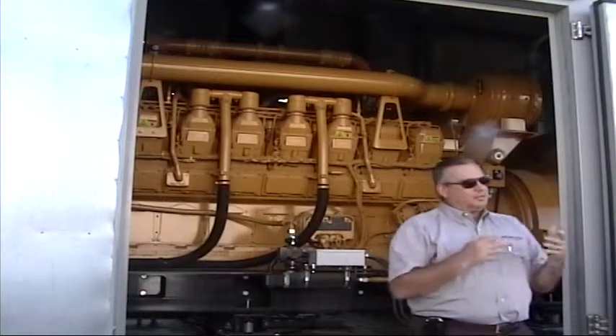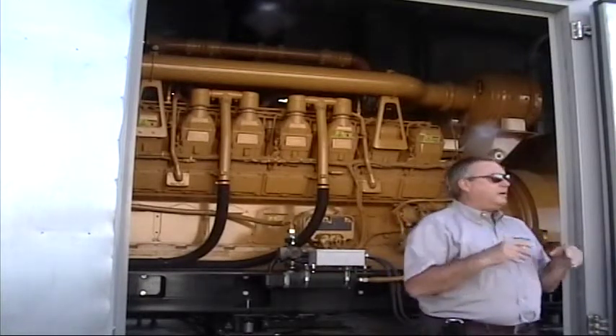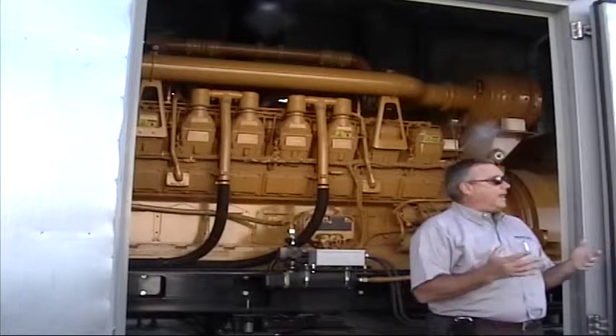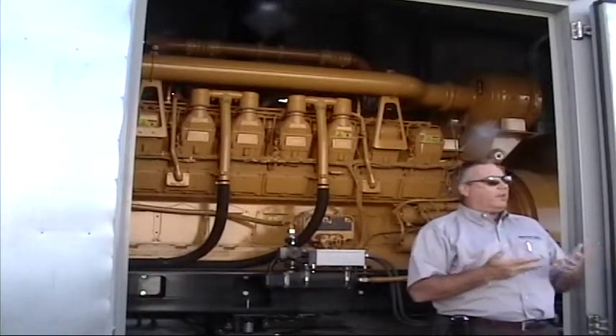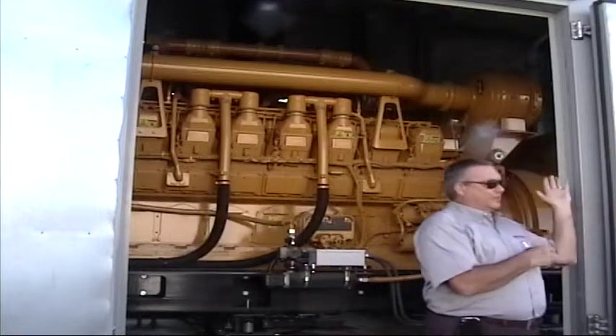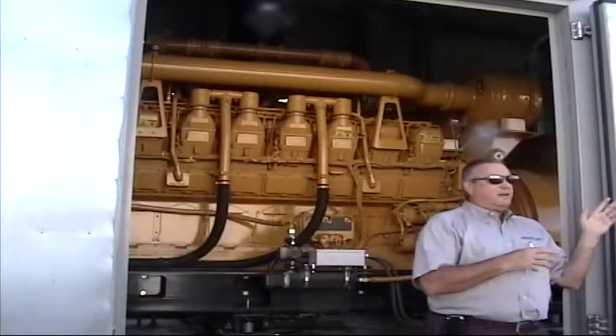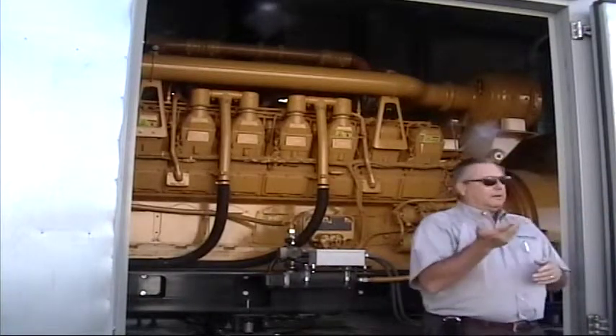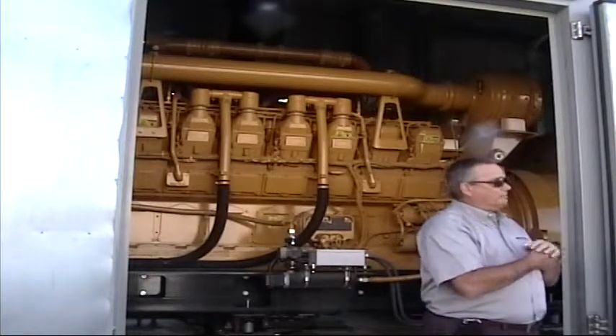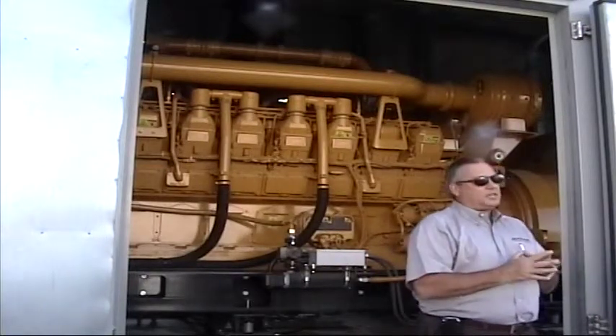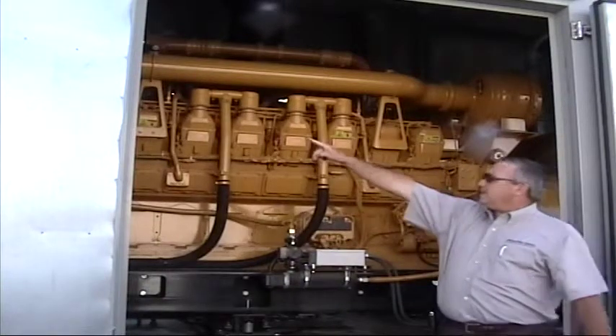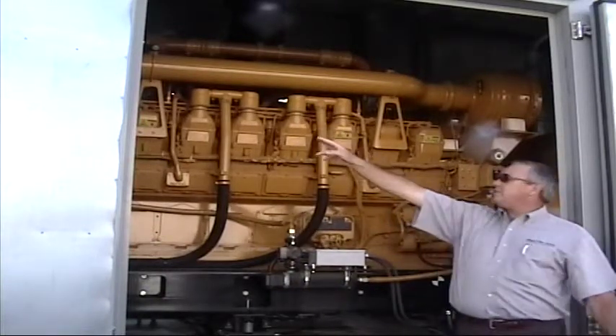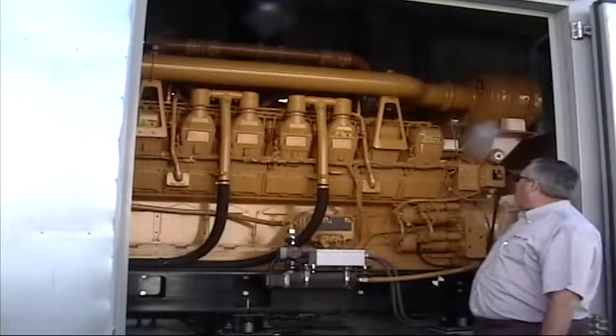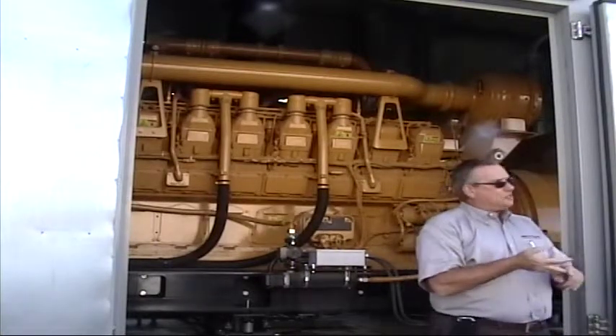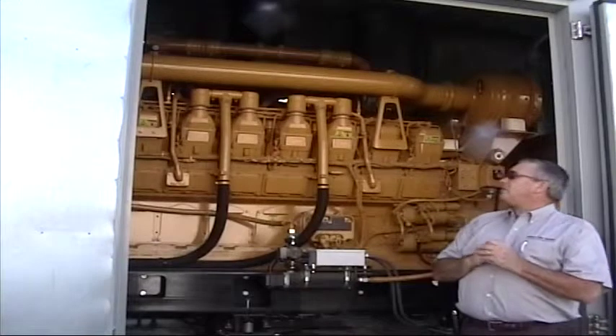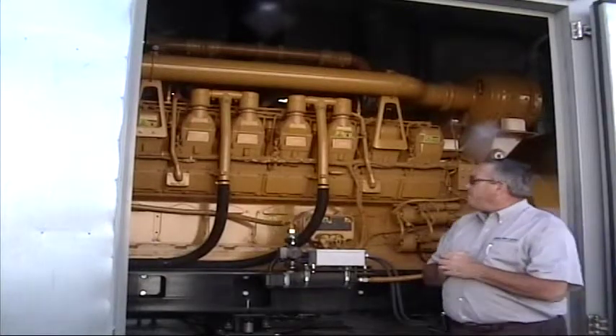A lot of the faults we get on them are from a sensor, and they do annunciate, which is how we can tell when things are going on. Sometimes you can tell by looking at the panel, and we'll get to that, or you may not be able to tell, and that's where a technician has to come out, hook up the ET, and find out what's wrong with the engine. So just so you know, I'm looking up here and I see the pressure sensors on the fuel filters. You'll see sensors all over, temperature sensors and pressure sensors, and they all send signals to the control panel.